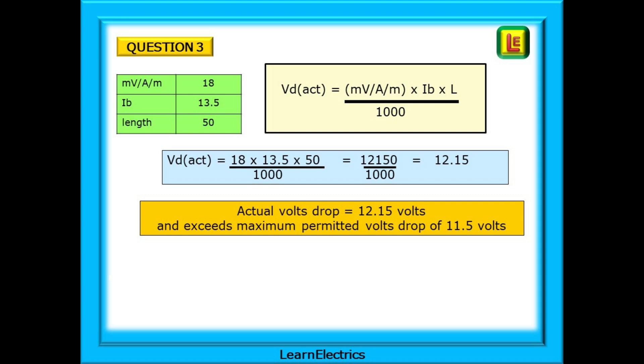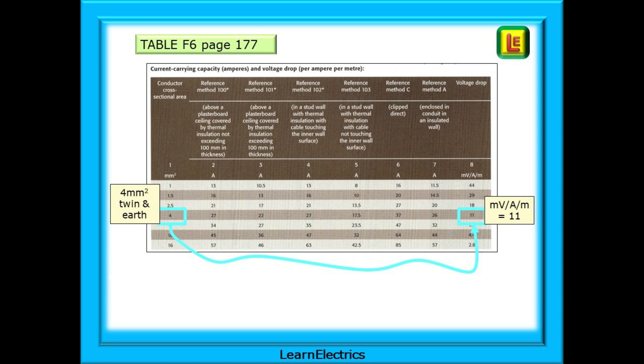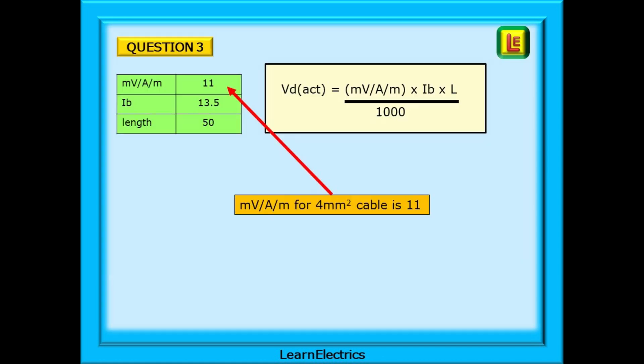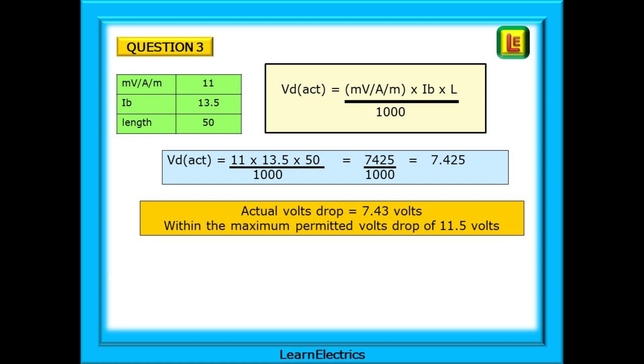What can we do? That was 2.5mm cable. Let's try again with 4mm cable. Just follow the same process. Start by finding the number for 4mm cable on page 177. The MVAM for 4mm cable is 11 and we already have the other two variables. Back to the calculator and this time our answer comes out at 7.43 volts actual voltage drop. So we should use 4mm cable as this gives an acceptable voltage drop.